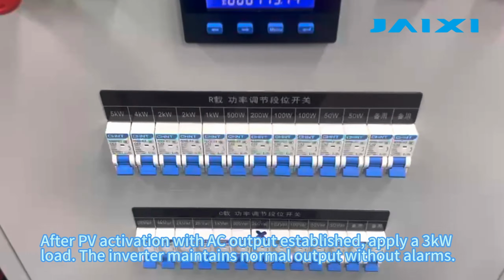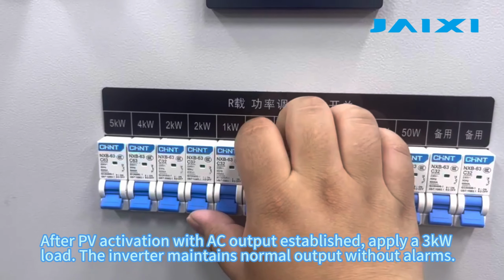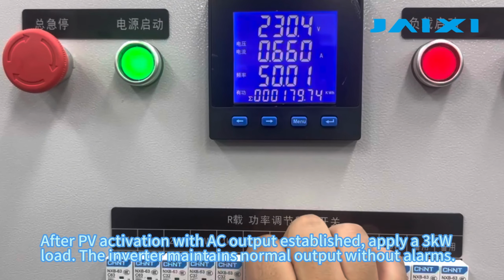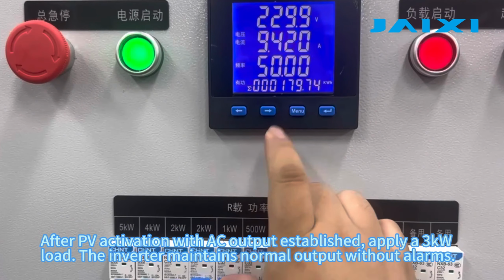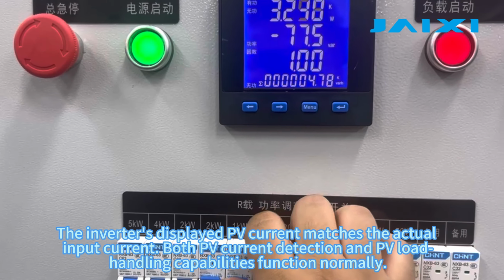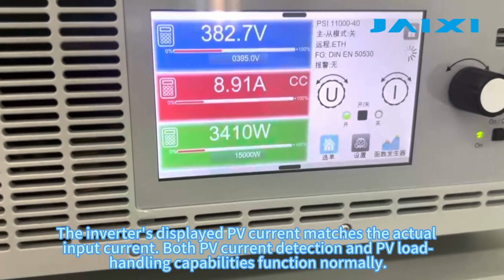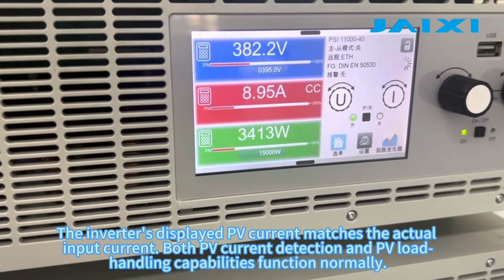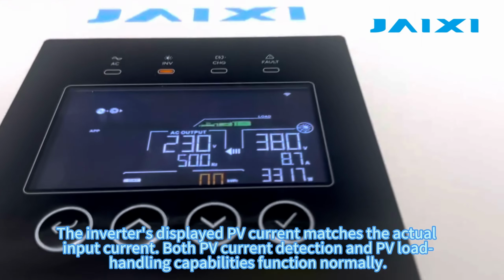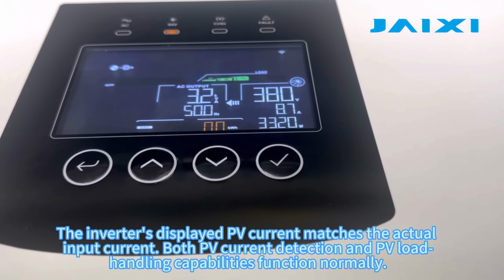After PV activation with AC output established, apply a 3 kilowatt load. The inverter maintains normal output without alarms. The inverter's displayed PV current matches the actual input current. Both PV current detection and PV load handling capabilities function normally.